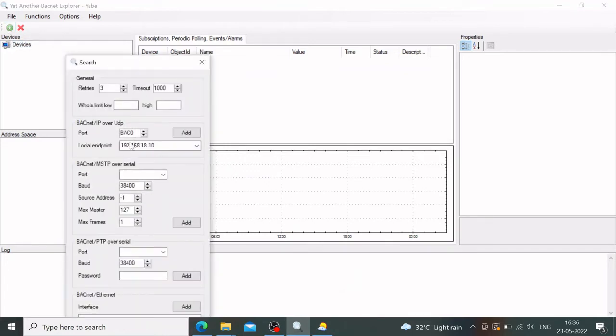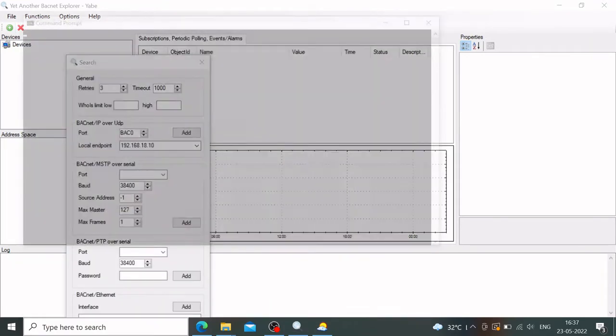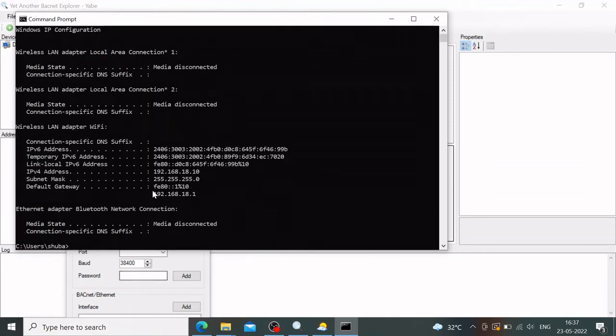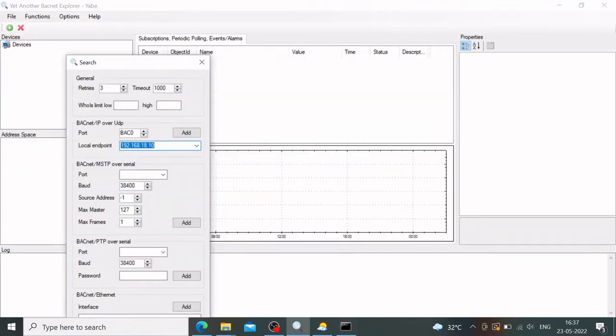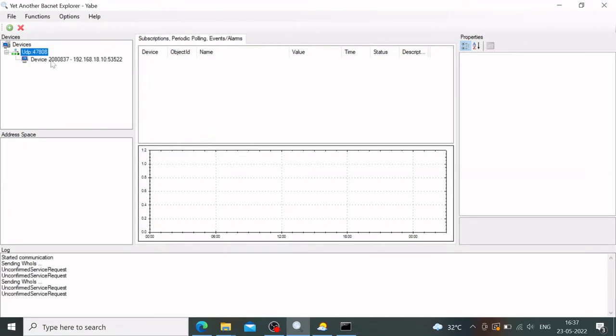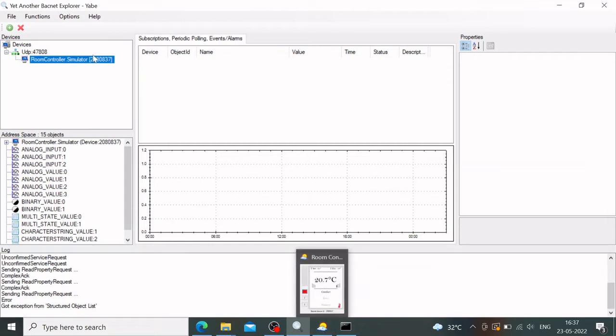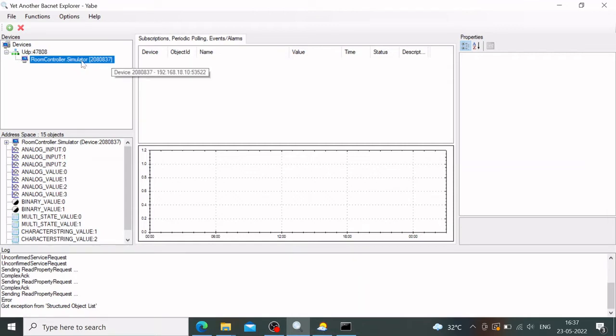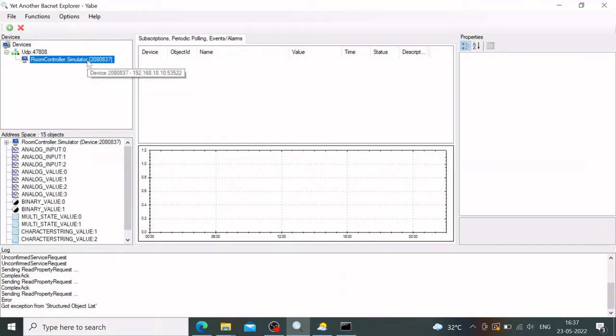In YABE, click 'Add Device.' Enter the local IP address of your machine — on Windows, run 'ipconfig' to find it. In my case it's 192.168.18.10. For the port number, use BAC0, which in decimal is 47808 — that's BACnet's default port. Click Add. The room simulator device is detected immediately, running on IP 192.168.18.10 at port 53522. That's how you access this BACnet device.